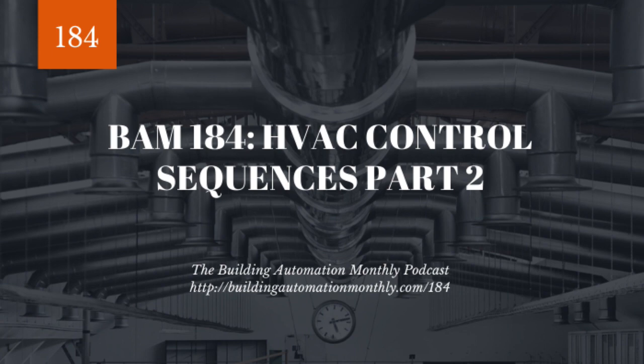So here's the big difference, right? With a single zone rooftop unit, most of the time, not always, but most of the time, these are considered packaged units. Everything's self-contained. It's all packaged together. And as a packaged unit, it has DX cooling, and it also has a typically gas heat. Okay, so DX cooling and gas heat. Now, what's going on here is that we're driving, once again, based on zone temperature. Okay, we're driving based on zone temperature, and this zone temperature is going to drive our heating and cooling. But we also have a supply fan, right?